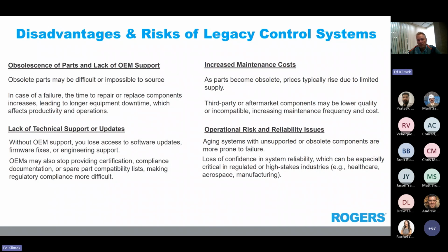Some examples of obsolete parts: analog panel instruments, like analog pressure, flow, and temperature gauges, were replaced with digital HMIs, SCADA interfaces, and smart transmitters. Mechanical linkages and cam-based control systems are obsolete now. Mechanical trip mechanisms and cam-based surge control systems were replaced by software-based anti-surge algorithms and DCS or PLCs. Relay logic panels are now obsolete. They were hardwired electromechanical relay systems. They are now replaced by PLCs or DCS systems.